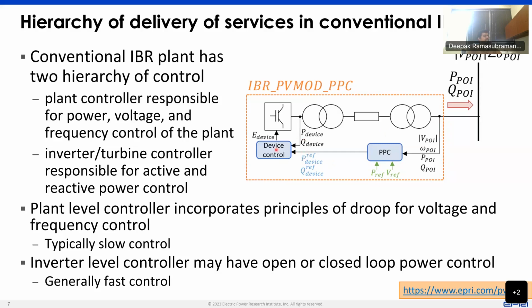So essentially the inverter is listening to the power plant controller, and the power plant controller tells it, hey, we see this voltage event on the system, the voltage is reduced, so increase your Q output so that you can help bring the voltage back up. This hierarchy of control is usually at the plant level, but it can be incorporated into the device level also, wherein instead of looking at the point of interconnection terminal quantities, it can look at the inverter terminal quantities and provide the same response. So that is how a conventional IBR and an enhanced IBR can provide both voltage and frequency control.